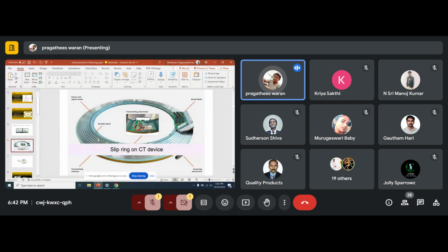Here, the power is transferred through carbon brushes. There will be no wire-to-wire contact between the stationary and the rotational part of the scanner. Through these carbon brushes, the power gets transferred from the stationary part of the machine to the rotational part of the machine. So what is the advantage? We no longer need to expose a patient too much.